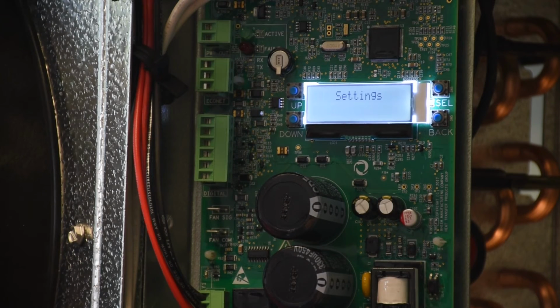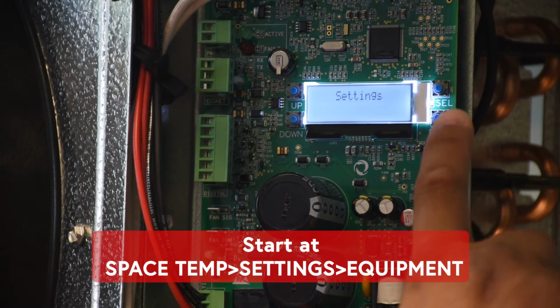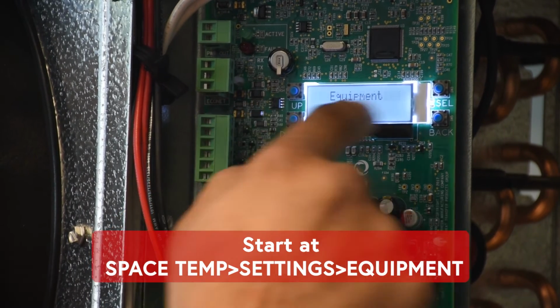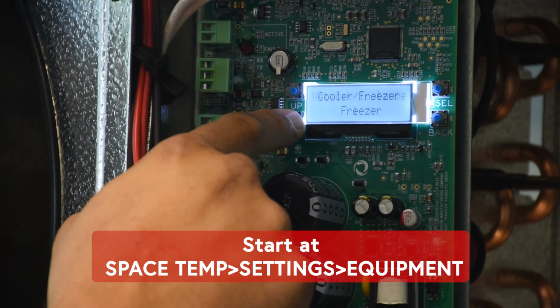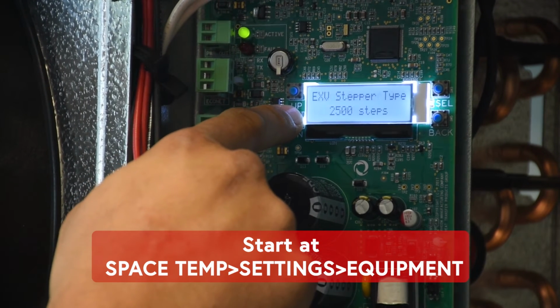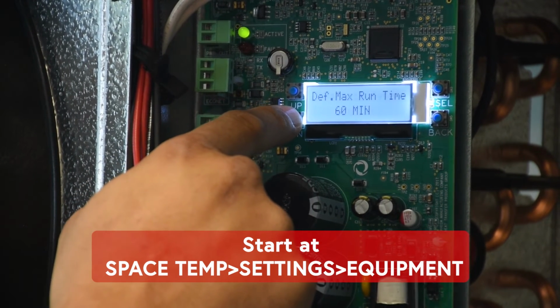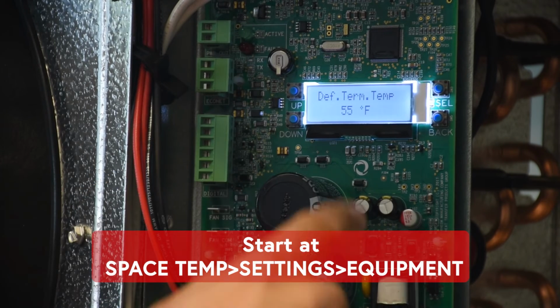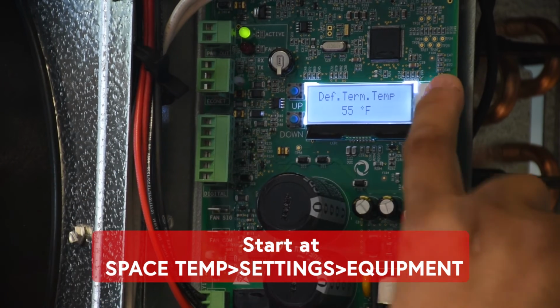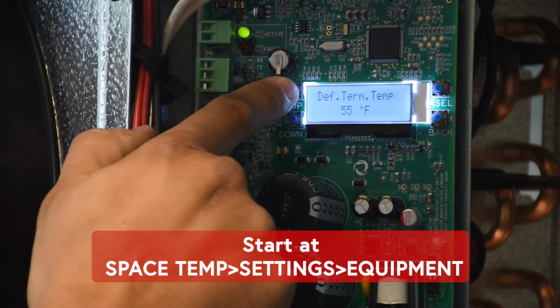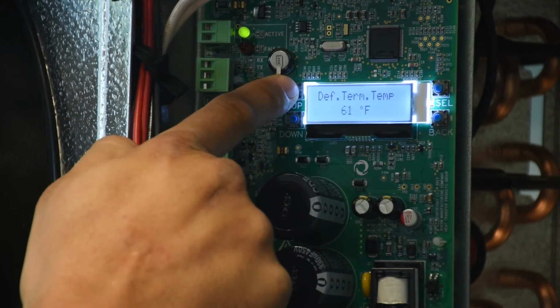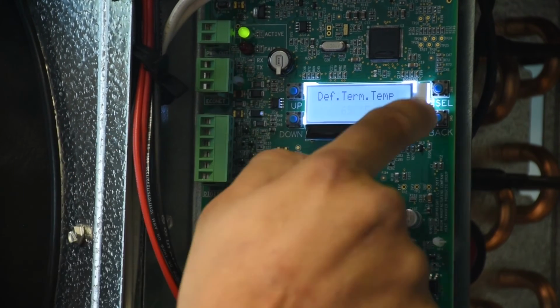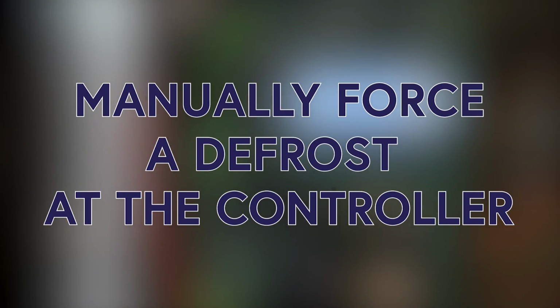To change your defrost termination temperature, again, we would go to settings, scroll down to equipment, and then look for the defrost termination temp setting. And that is it right there. And again, hit select, the number will start flashing, and then you can adjust it to the desired number, and then hit select again.